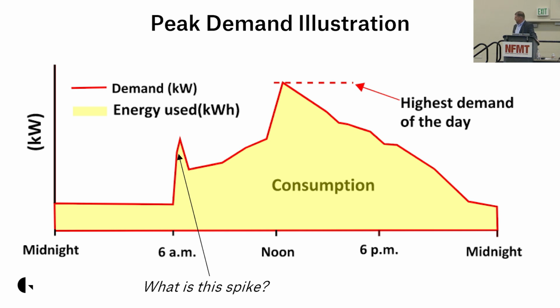Your demand is determined by whatever the highest amount of usage is per day. What your electrical company wants is, once a month or whatever your pay period is, the highest possible demand you've hit that month, and there's a prorated amount they bill you for. It's highly substantial to pay that demand charge - when you're talking cents per kilowatt for energy, you're talking $15 to $25 per kilowatt for demand.